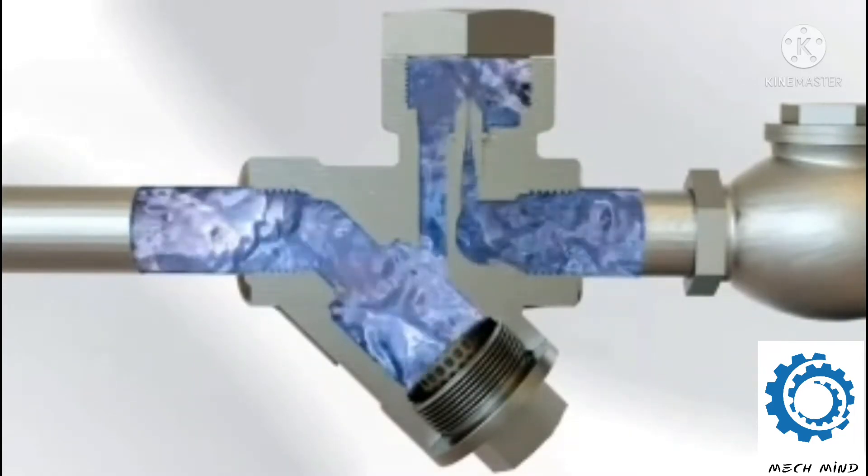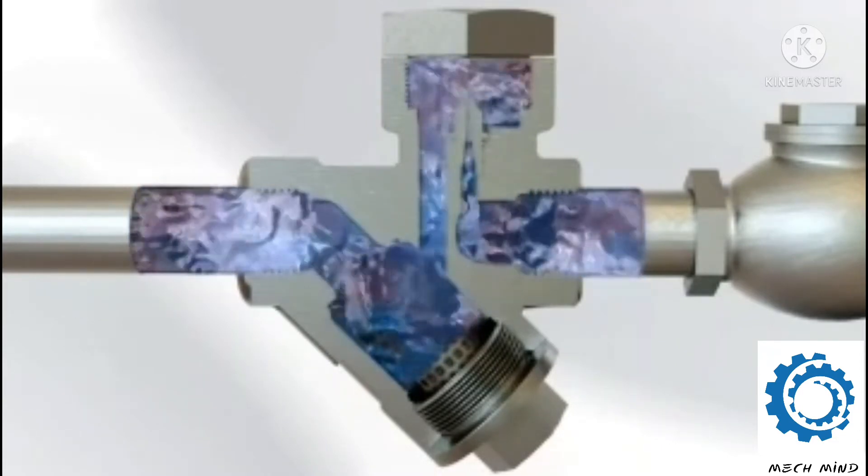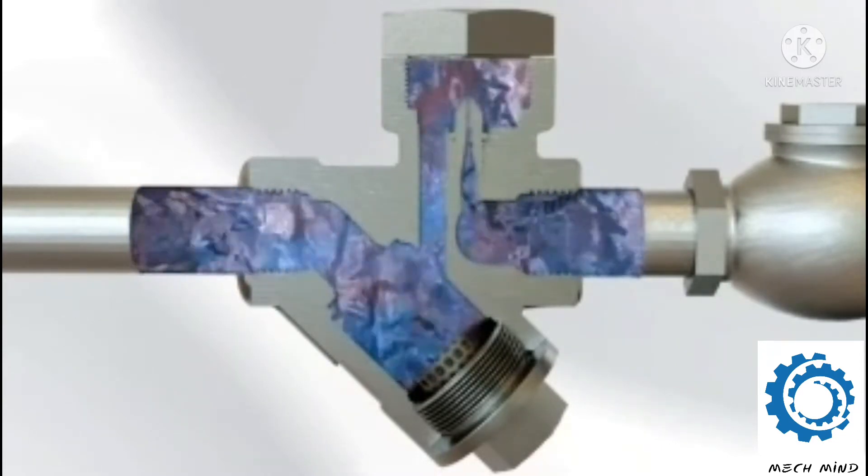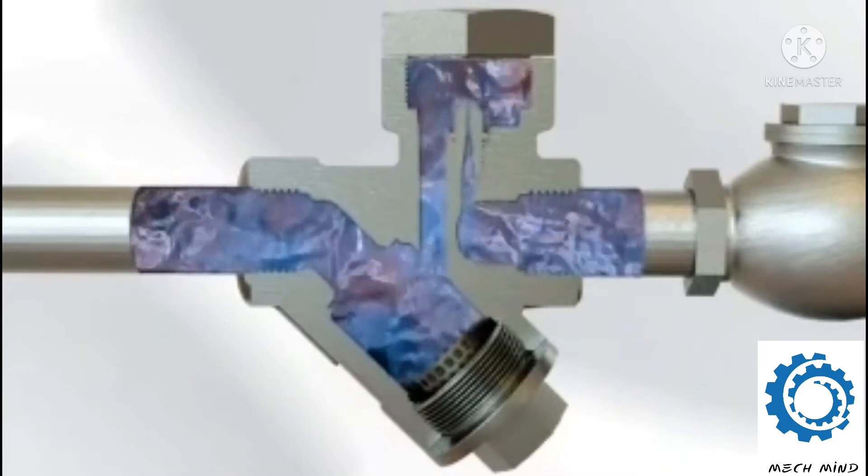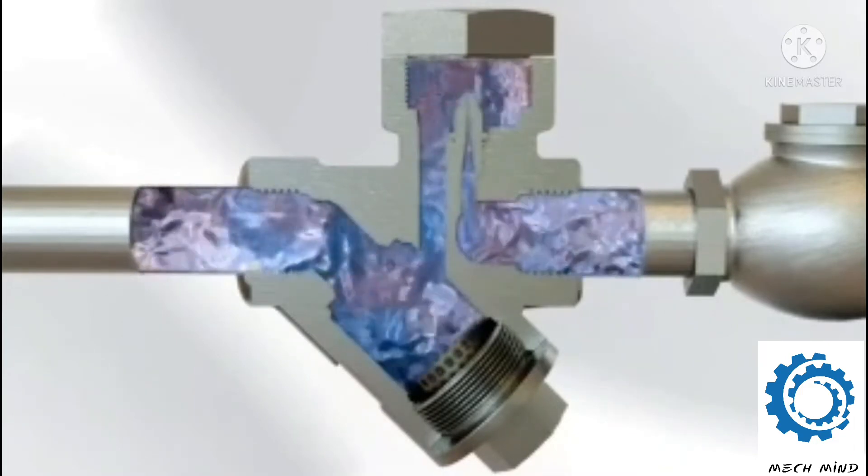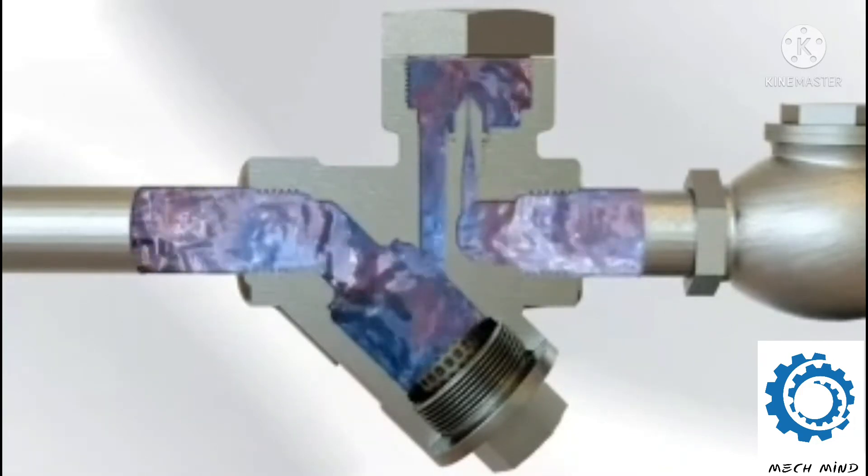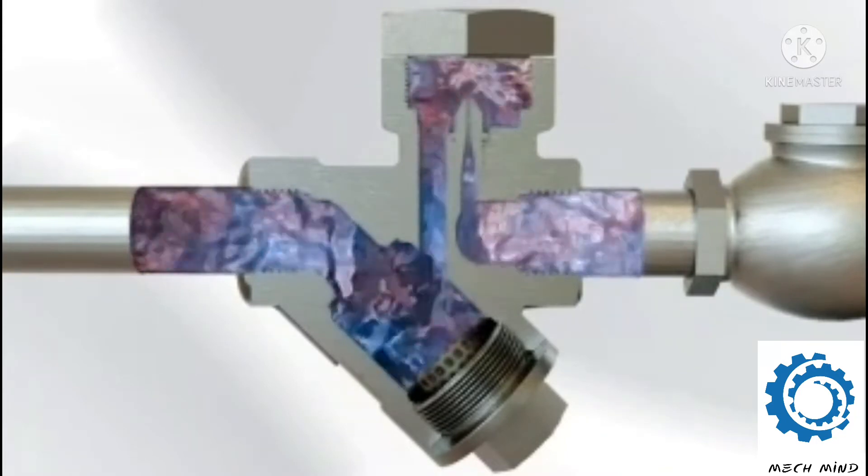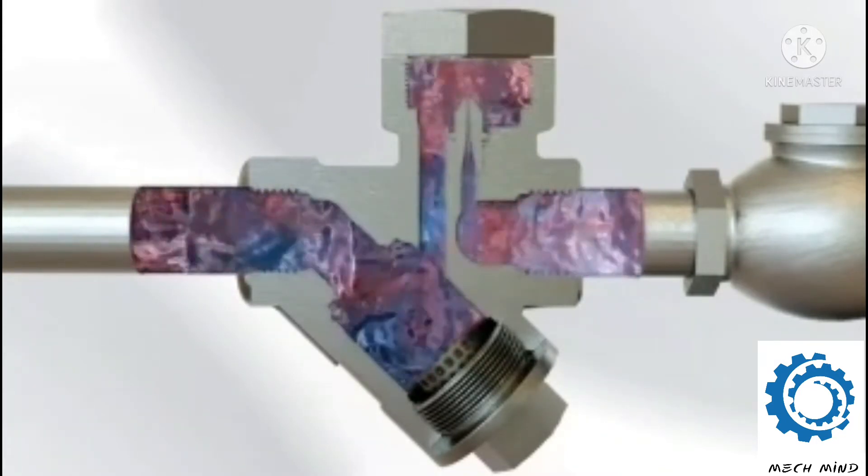Once all the cold condensate and non-condensable gases have been ejected, steam and hot condensate reach the delta steam trap. As the steam continuously condenses to hot condensate in the pressurized steam system, it is fed to the steam trap by the pressure in the system.